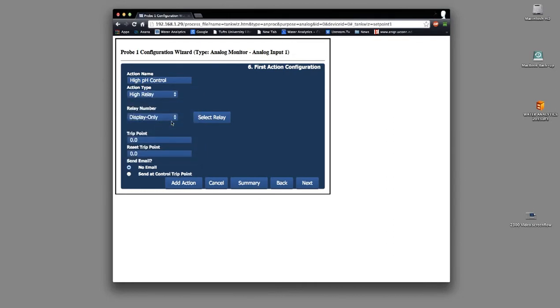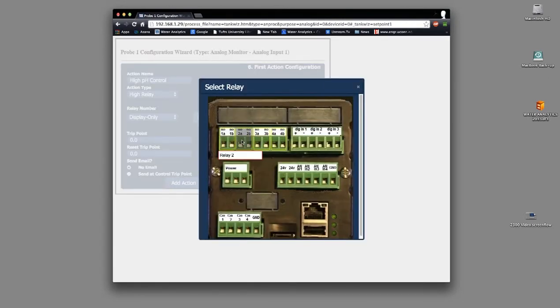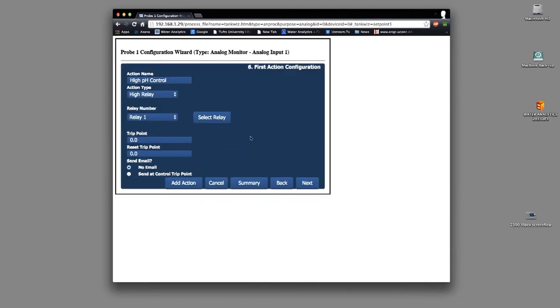Now I have to choose one of 4 available relays, or it could be greater if you had an optional add-in card that has additional relays. That process is just like choosing a probe input. If I click on the select relay button, I get a picture of the relays, each one surrounded by yellow rectangles. I'll choose relay 1. And just as we did before, I could have also chosen that from a drop-down menu. The trip point is clearly 8.5. We don't want our process to go above a pH of 8.5.